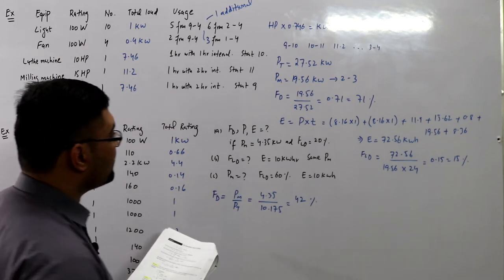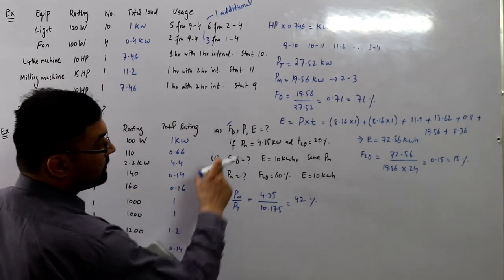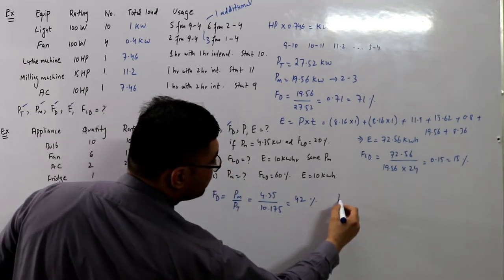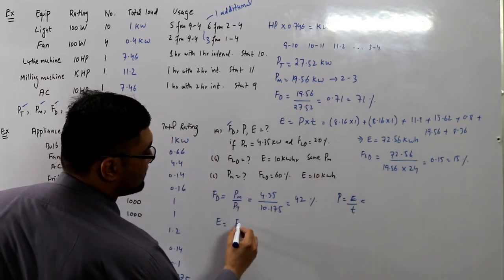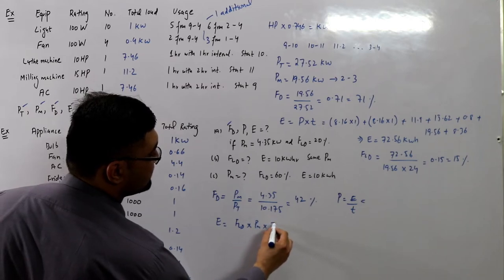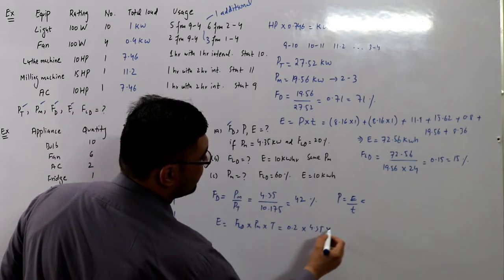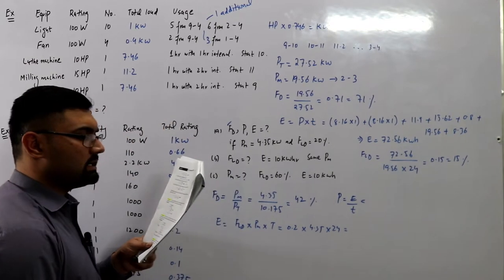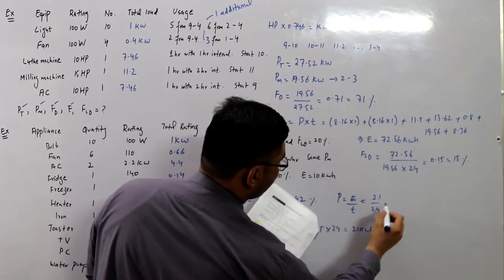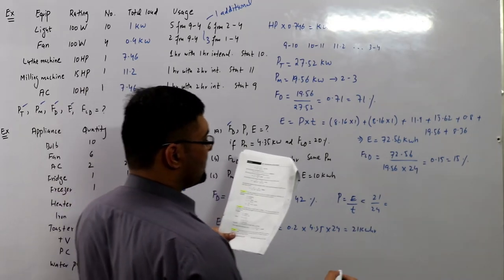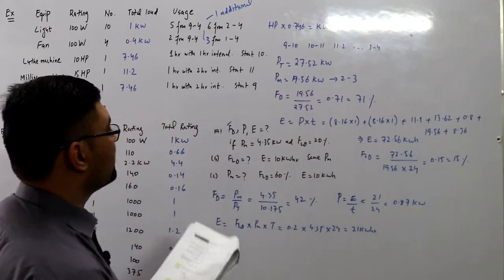For daily energy consumption, first find e from the load factor formula: e = fld × maximum demand × time. fld is 20%, maximum demand is 4.35 kW, time is 24 hours. The number of energy units is 20.88 kilowatt hours, approximately 21 kWh. The average load p = e / t = 21 / 24, which gives 870 watts or 0.87 kilowatts.